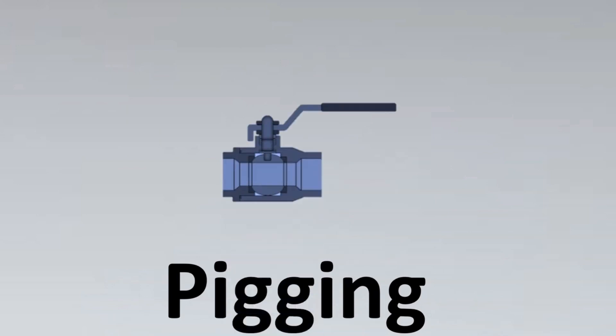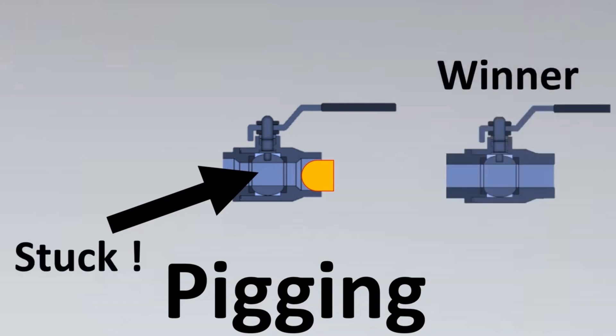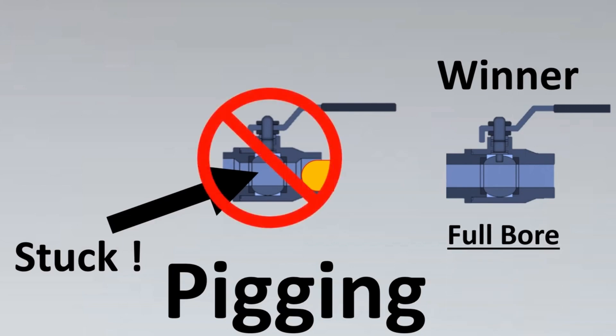So how does pigging relate to full bore vs. reduced bore? If you use a reduced bore valve and insert the pig, the pig is going to get stuck inside the valve — because the pig size matches the line ID, but the reduced bore has a smaller opening. Whereas with a full bore valve, the entire pig can pass through. So for pigging applications, full bore valves are required and reduced bore cannot be used.